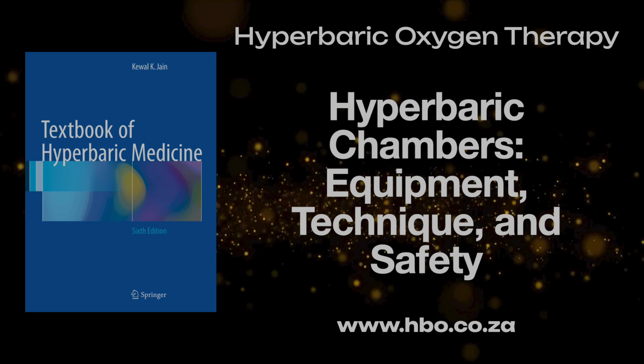Keeping oxygen levels down, keeping the chamber atmosphere below 23% oxygen. Having fire detection, manual and automatic. And fire extinguishing systems, usually pressurized water deluge systems, handheld hoses, plus regular drills. NFPA 99, Chapter 19 covers this.